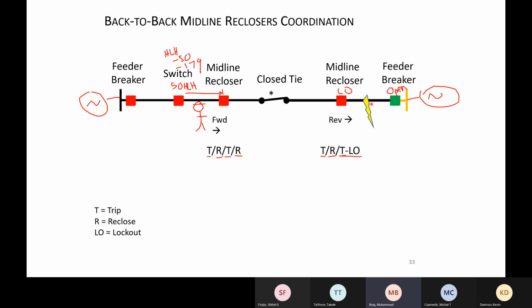But we have to change the recloser setting. Then we have to make one shot here and two shots there. Nope. The relays automatically do it because they're just using is the fault in front of me or behind me. Oh, okay. So there's no setting changes. The only change is the relay. We had to add PTs to our reclosers.